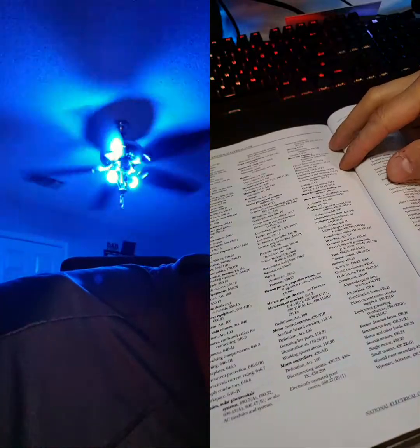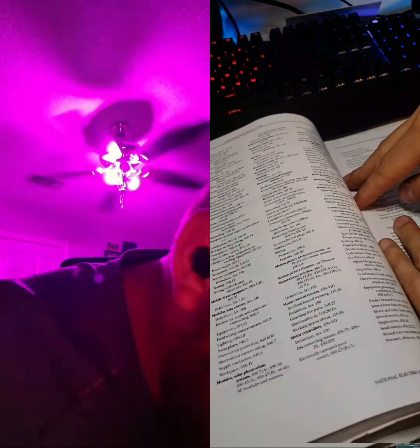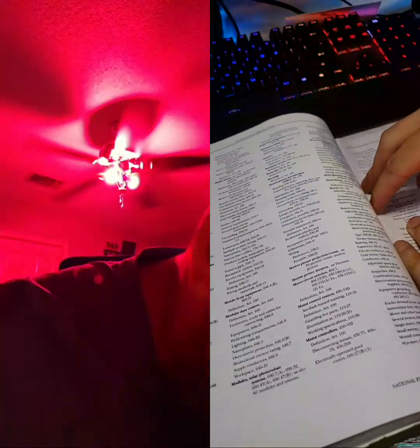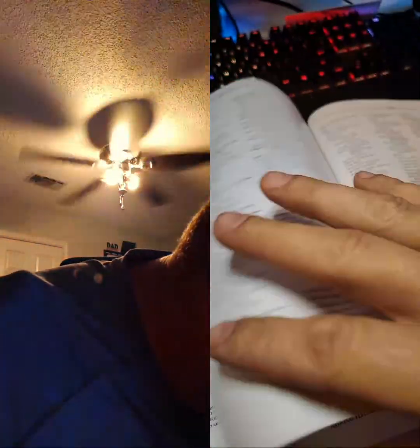And that's why if you have an equipment room that has 1200 amps or more in it, and you're less than 25 feet from the nearest door, you have to double your distance of working clearance. And we'll see that in a second in the exact same location that you're going to find this code.